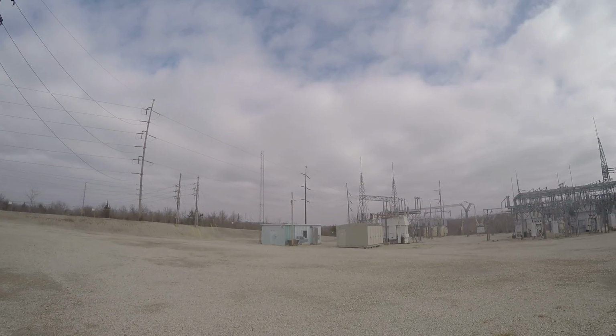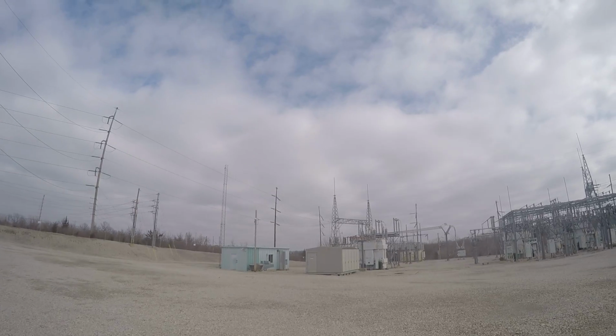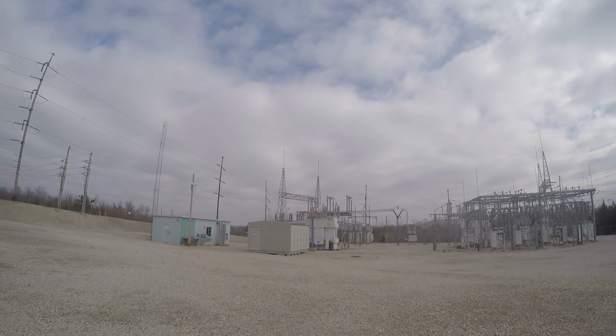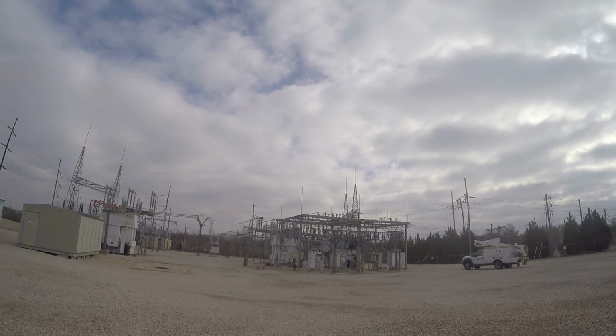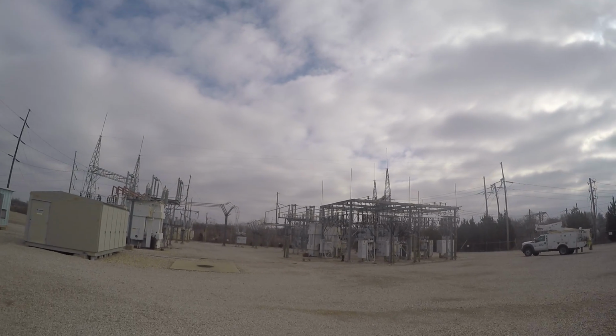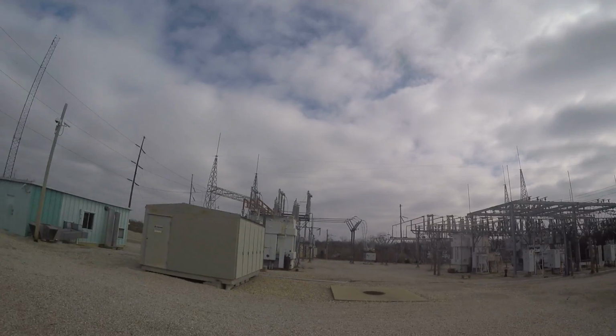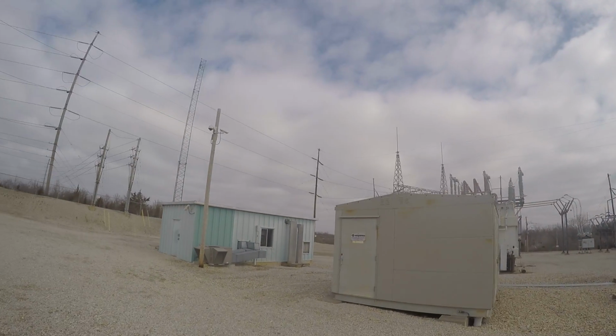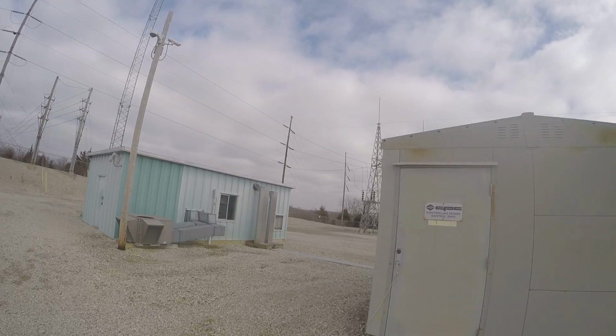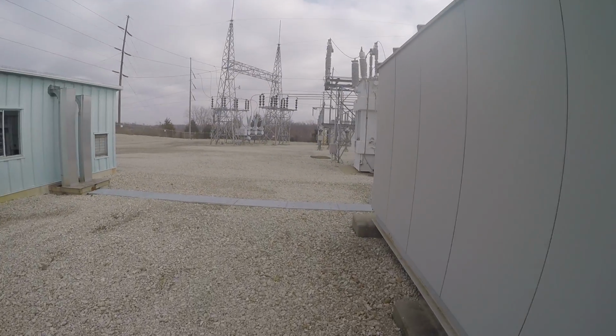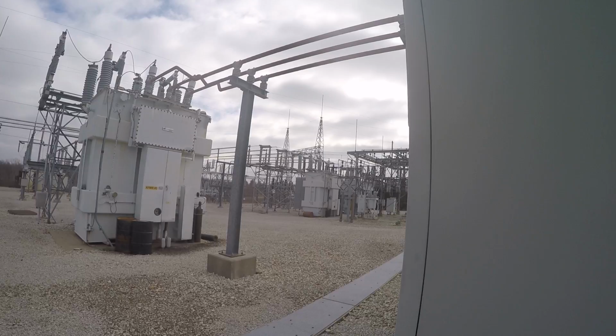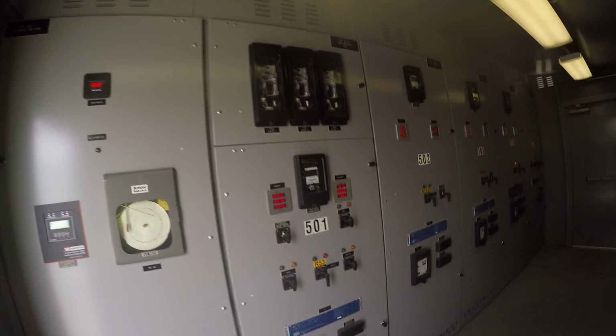Run over here and we'll look at a different type of breaker. In the same sub, we had the oil circuit breaker that went straight to the overhead wire. We got one that goes to underground wire and then comes up a terminator. Then we have these in the building, air circuit breakers. They all do the same thing, show fault. See if them lights get going and we can see in here. Try and prop it open.